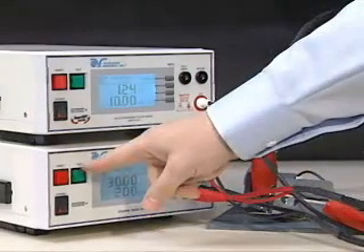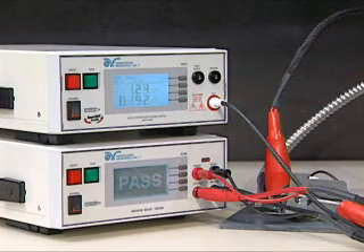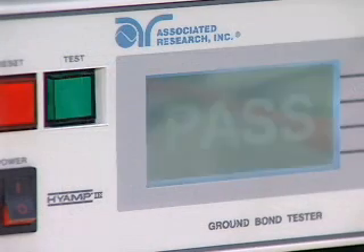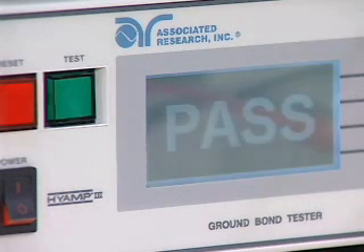You must start the test from the HYAMP III. Never touch the device under test while the test is in process. Once the ground bond test passes, the HiPot test will automatically start. At the conclusion of the tests, pass-fail results will be indicated.